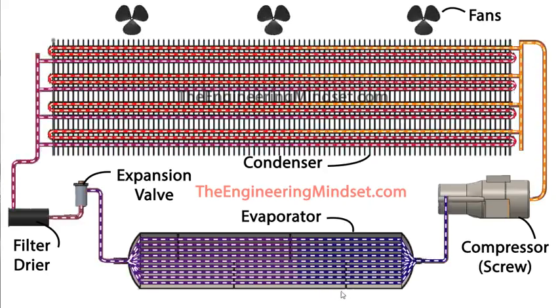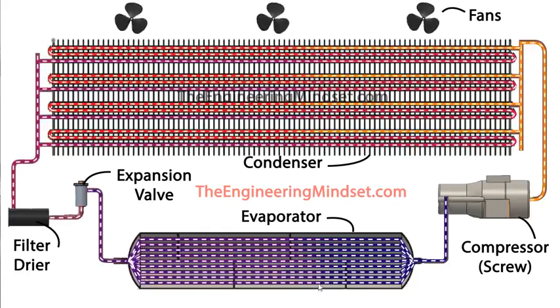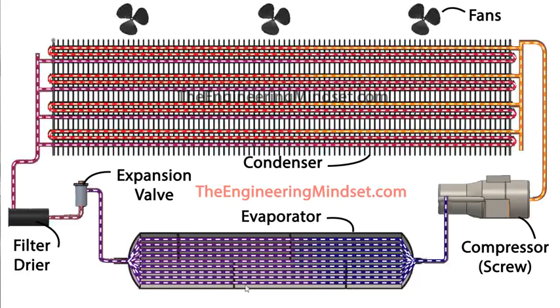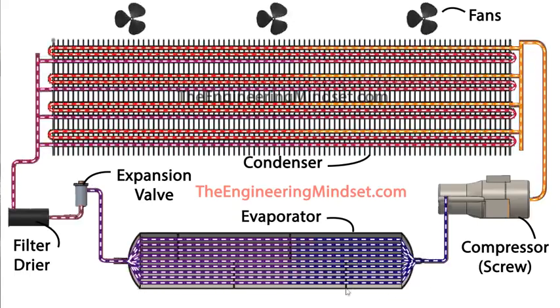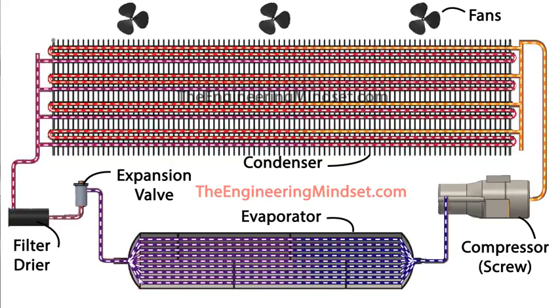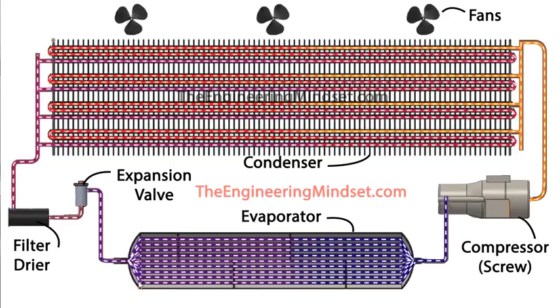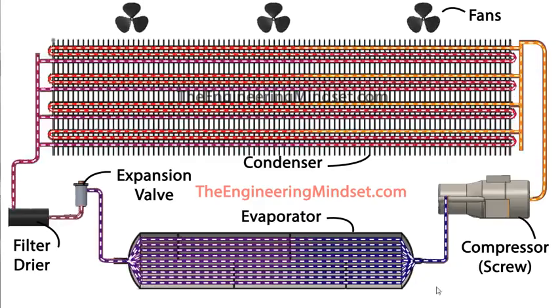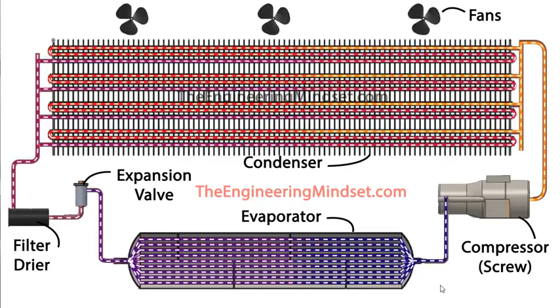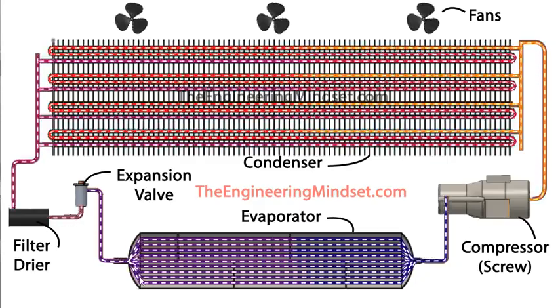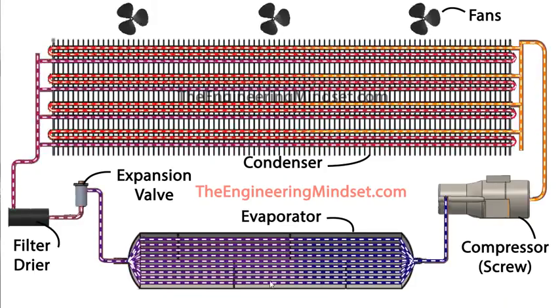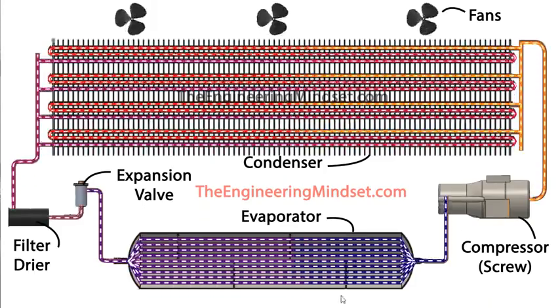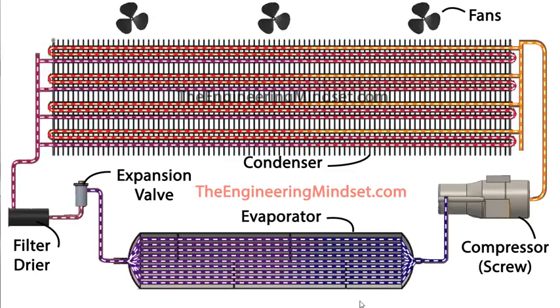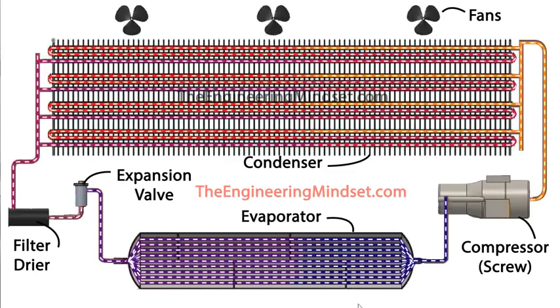Now this is known as a shell and tube heat exchanger. So one fluid would be in the tubes and another fluid would be in the shell. In this case the refrigerant is going to be the one that passes through the shell. This is slightly different to a water-cooled chiller, where it would actually be the other way around. But anyway, the refrigerant passes through here and it will start to absorb some of the thermal energy that's coming in, and we'll have a look at that in just a second as well.